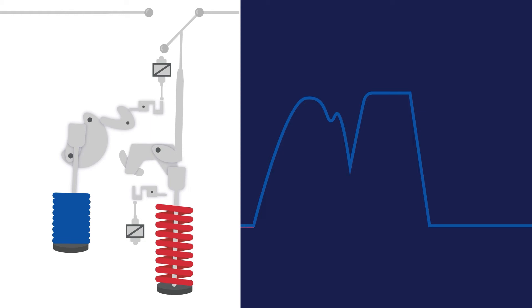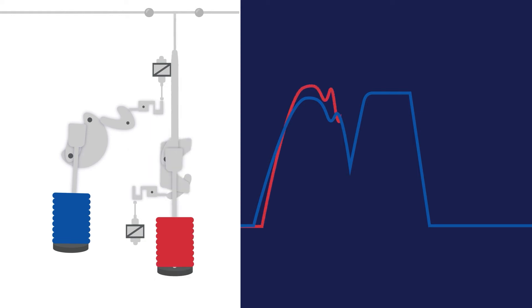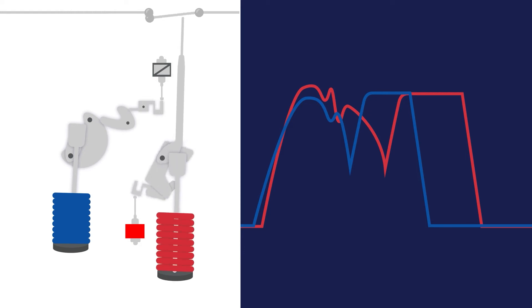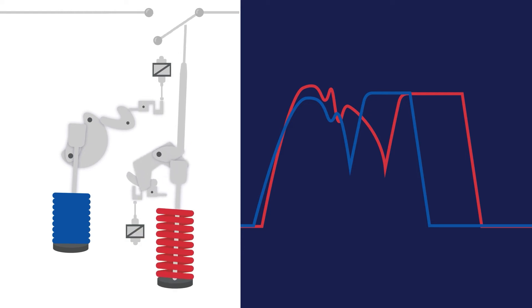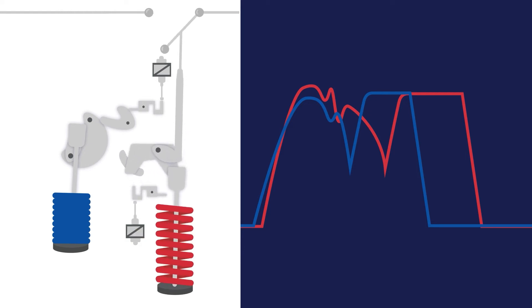Alternatively, should problems begin to develop with the latch, the point where the plunger strikes the latch would display a higher current level and the buffer point would move further to the right of the graph, indicating that the switchgear took longer to release the latch, delaying the initiation of the main cam.